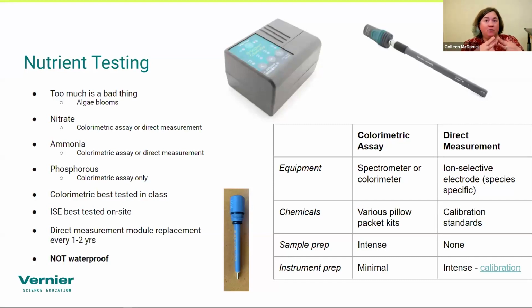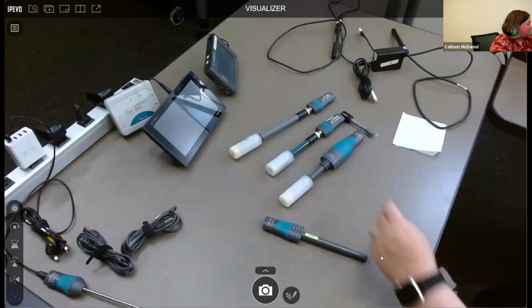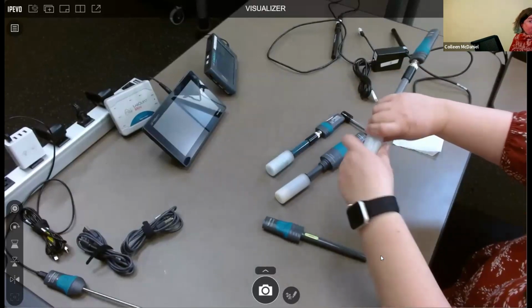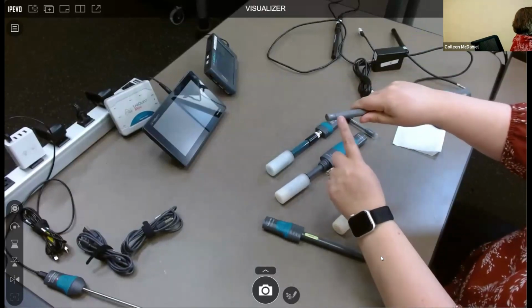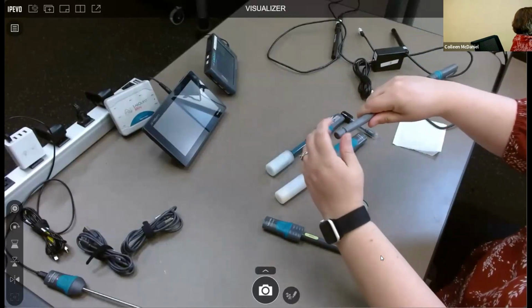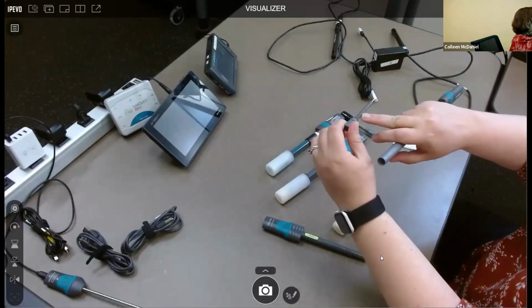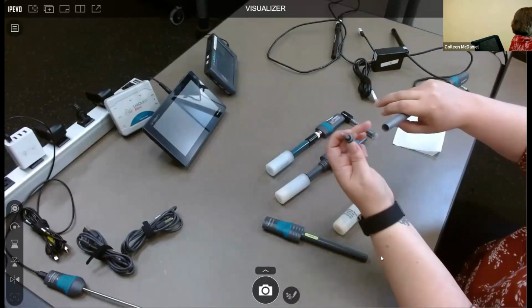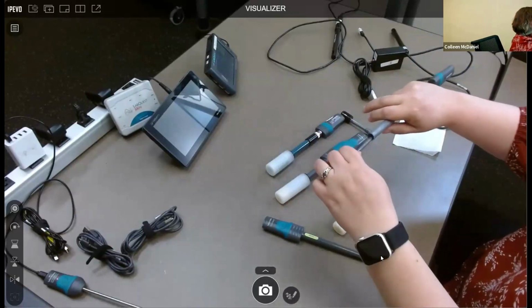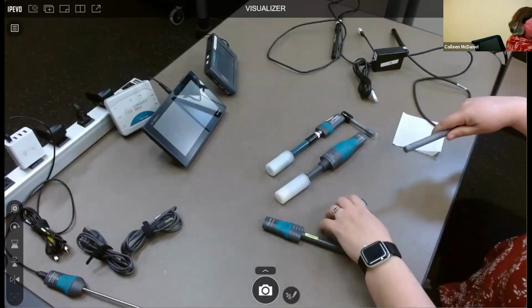The thing to keep in mind with ISEs is that they do have a module on them that does need to be replaced every 1 to 2 years. And that module has a shelf life. So what I recommend people doing is checking on their module. You can actually screw it off. I'll show you here with our visualizer. So on both the LabQuest version and the Go Direct version of the ISEs, you have a module on the tip here that actually unscrews off. And then you can look at a date that's printed on the side here. This one, for example, says November of 17. So that one is very expired and needs replacing.